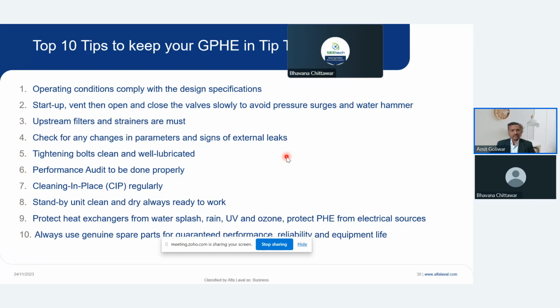CIP is a better practice, because for doing CIP you need not open a heat exchanger. So if you do CIP regularly and maintain it in the logbook, it helps in maintaining the equipment. You need not open it more frequently. Standby unit, use it whenever required. It's better to use it for alternate periods, and protect heat exchangers from water splash, rain or UV. And most important, it is mandatory to have earthing done on a plate heat exchanger, and always use genuine parts.